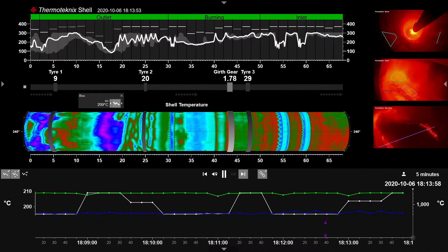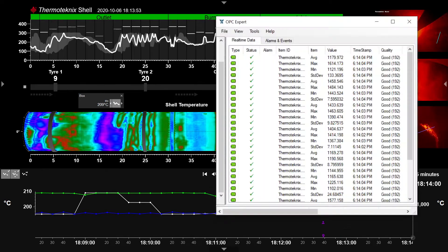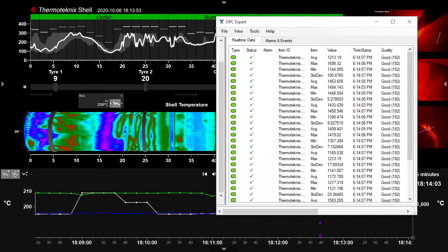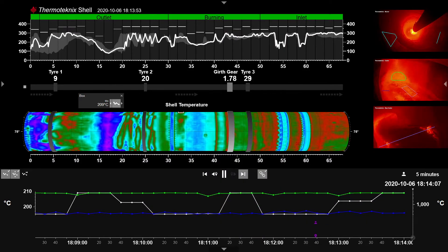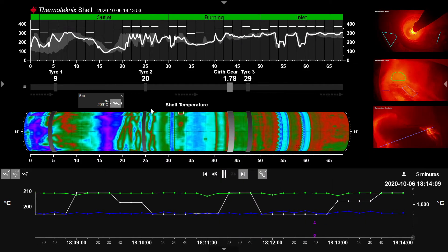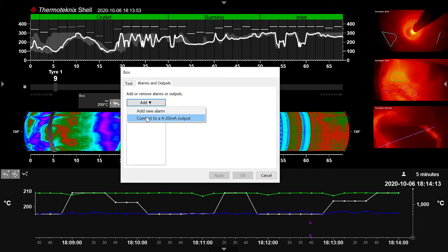Multiview Enterprise provides an OPC server to output real-time digital temperature data from shell scanner, burner and cooler cameras. Data measurement tools can also be linked to analog 4 to 20 mA outputs and closed contact relays.